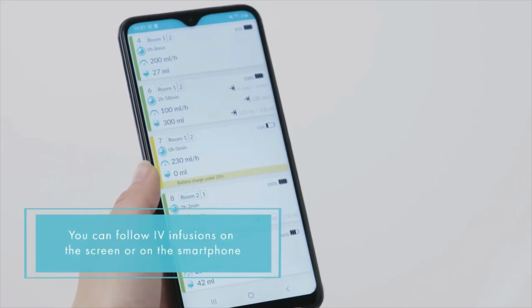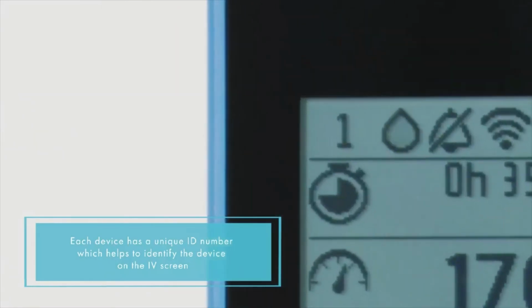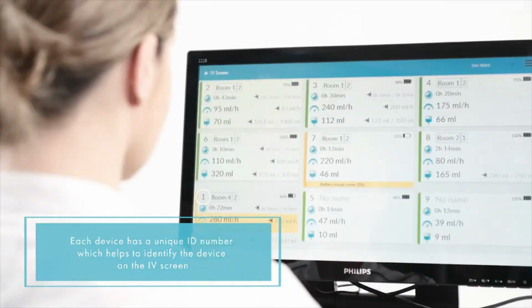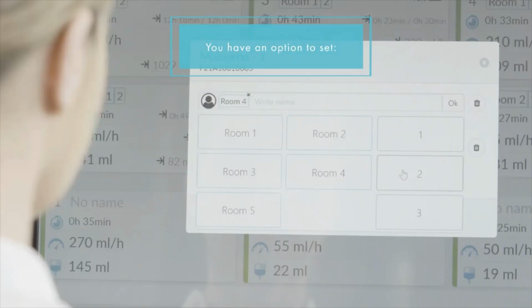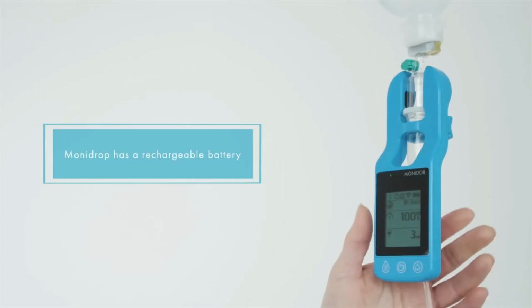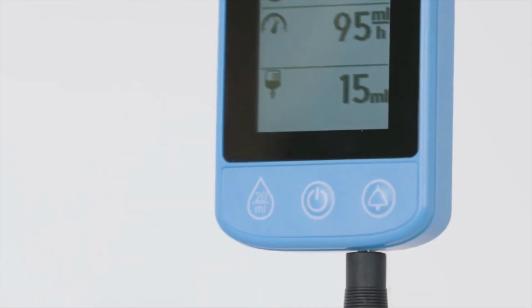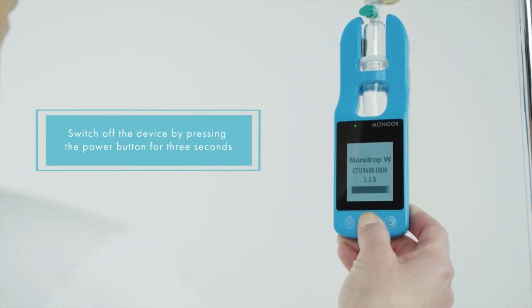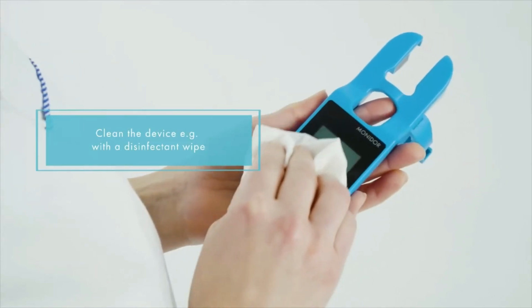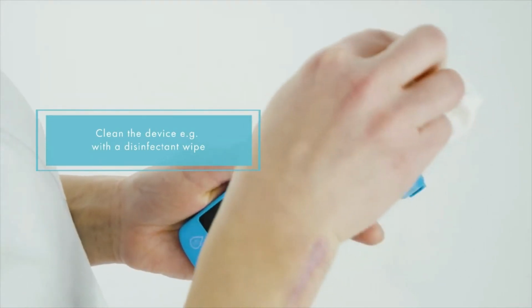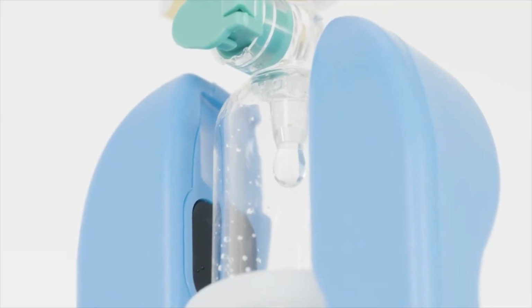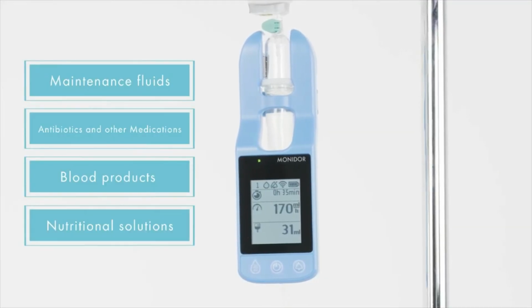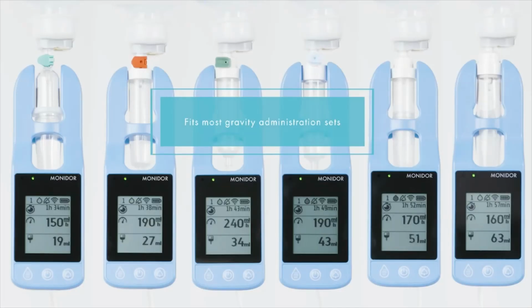When the Monidrop is switched on, the device data appears automatically to the remote monitoring IV screen. Each device has a unique ID number, which helps to identify the device on the IV screen. On the IV screen, each device can be assigned to a room location and to a patient's bed number. There is an option to set the target values for the fluid volume to be infused and the treatment duration. Monidrop has a rechargeable battery, and this can also be used at the time of charging. Switch off the device by pressing the power button for 3 seconds. Clean the device, for example, with a disinfectant wipe. Monidrop can be used to administer maintenance fluids, antibiotics and medications, blood products, and nutritional solutions. Monidrop fits most gravity administration sets.